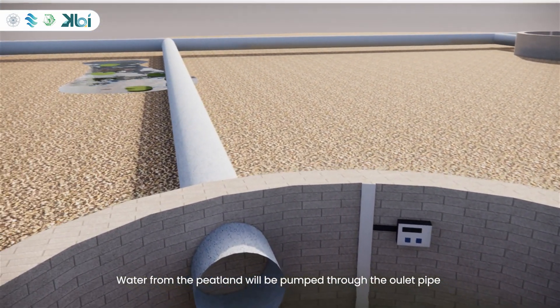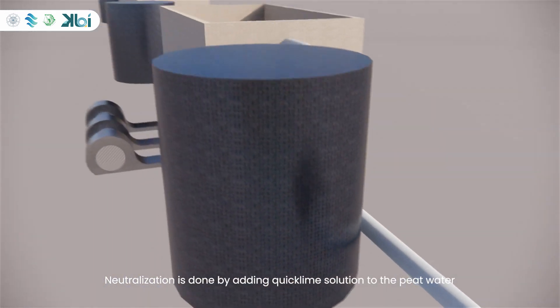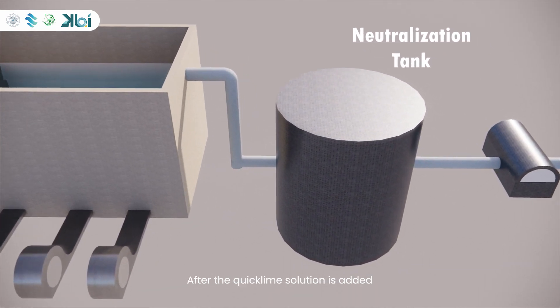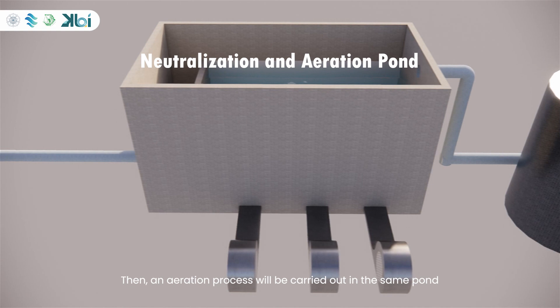Water from the peatland will be pumped through the outlet pipe and will then undergo a neutralization process. Neutralization is done by adding quicklime solution to the peat water, aiming to make the pH neutral. After the quicklime solution is added, the peat water will settle in the neutralization pond for a period of time. Then an aeration process will be carried out in the same pond, introducing oxygen into the peat water using an aerator to reduce the concentration of dissolved metals.